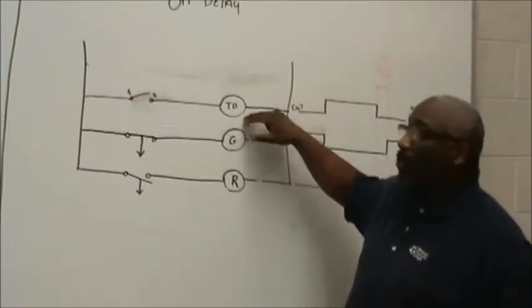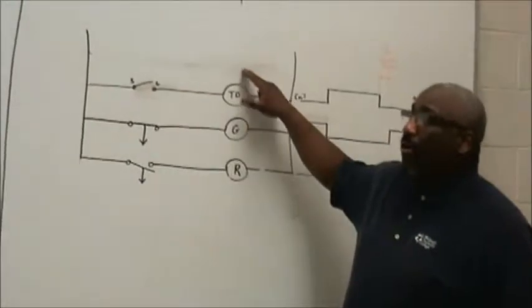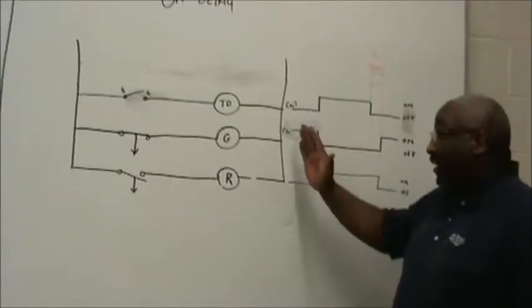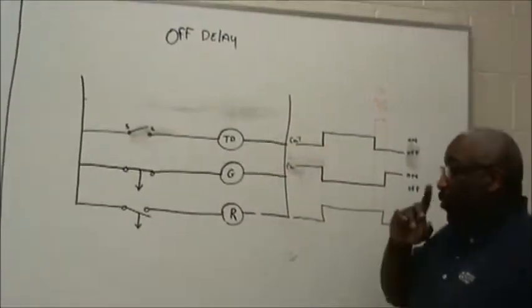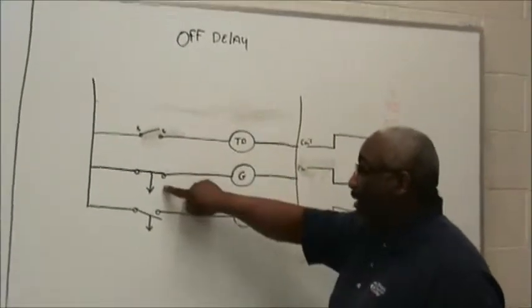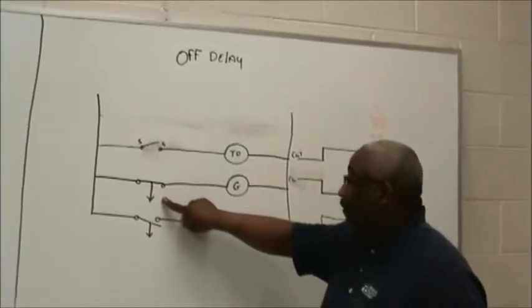The timer coil will not say off-delay or on-delay on it. Maybe you would find it in a spec sheet, but not in the ladder diagram. The way you tell what type of timer you're working with is by looking at the timer symbol.